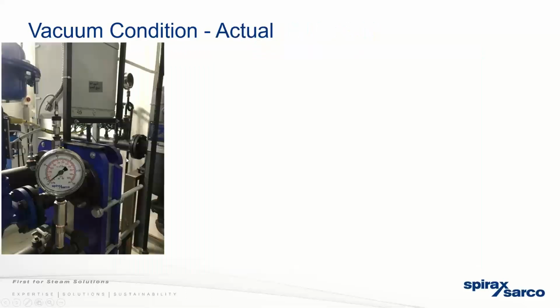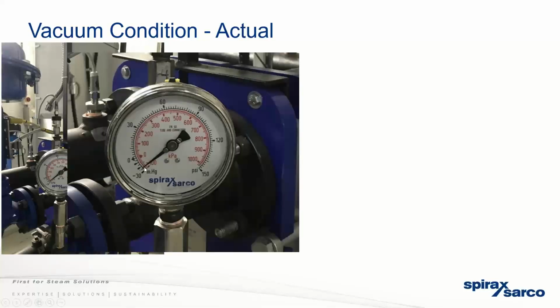So that's why it's a benefit to design a system to operate in vacuum. This picture is a close-up of one of those heat exchanger packages I showed earlier, with 100 psi steam going into this heat exchanger here. After the control valve, we're showing a pressure of over 20 inches of vacuum, although the system is supplied with 100 psi steam.